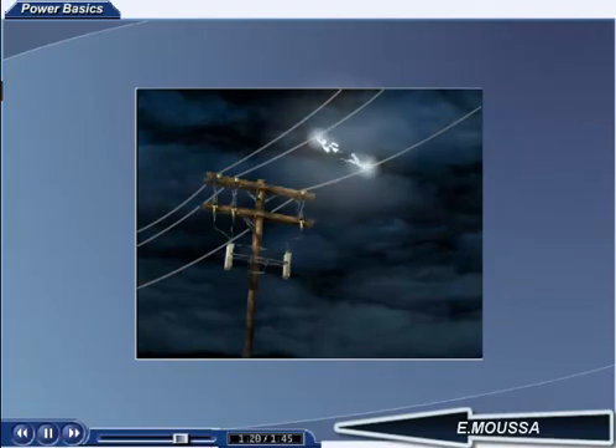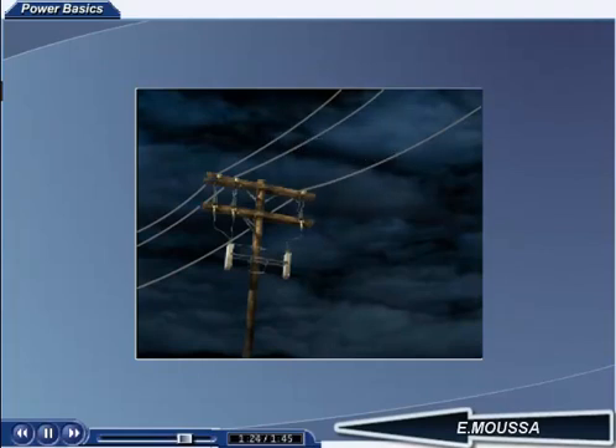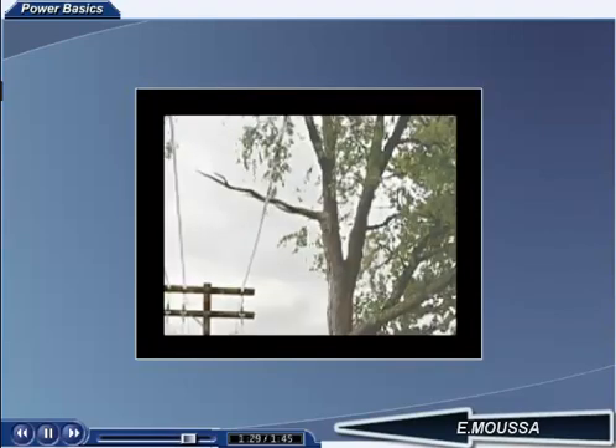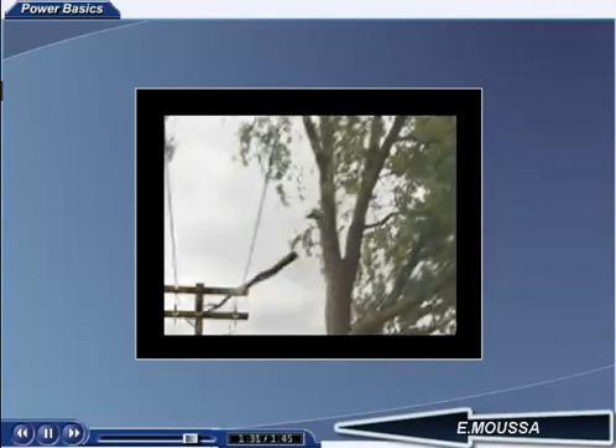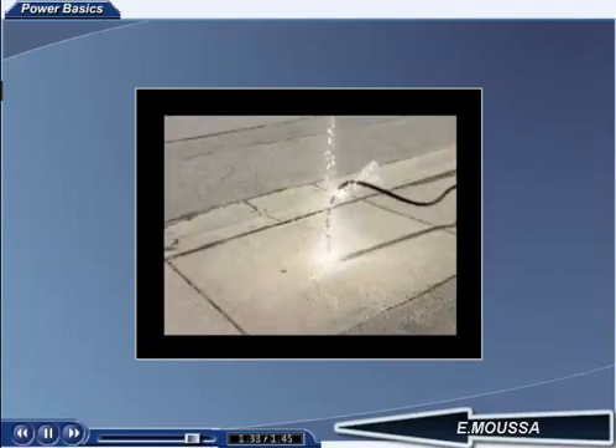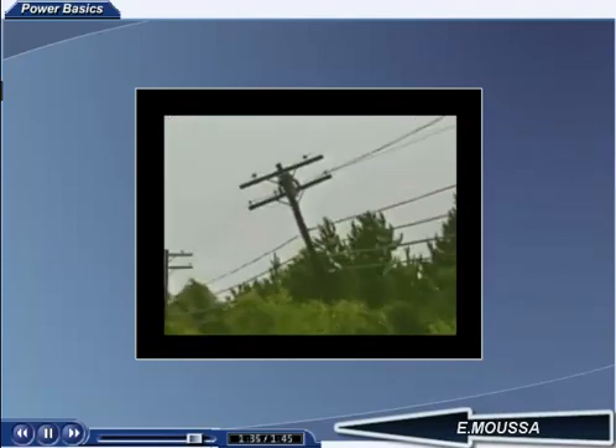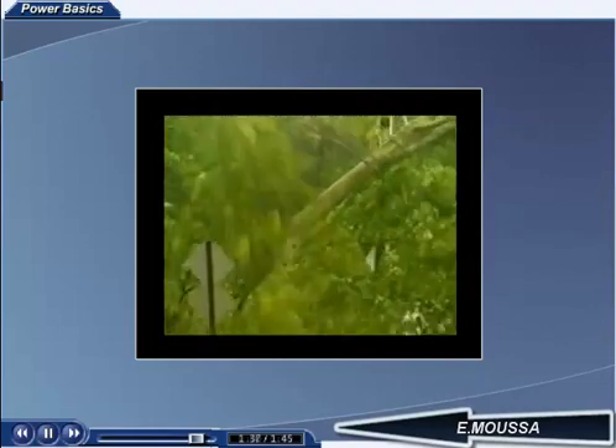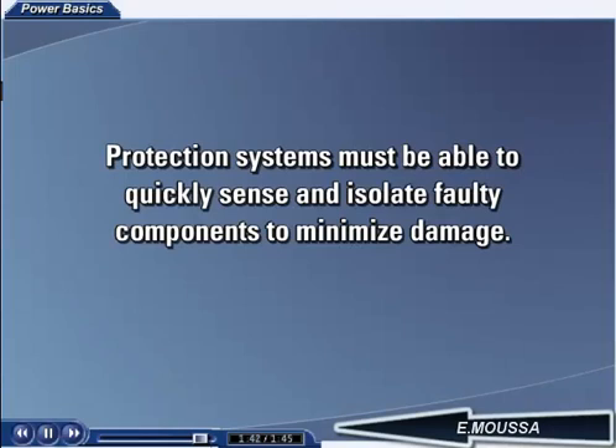In both cases, the protection system responds by removing power from the line for a period of time long enough to allow the ionized air to dissipate, and then reapplies power to restore service. Physical damage to a power system component, such as the transmission line or towers, are 2 examples of permanent faults. The protection system must be able to quickly sense and isolate the faulty components to minimize damage.